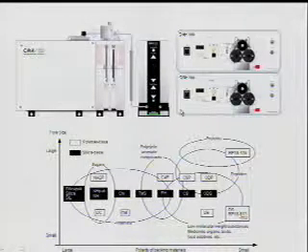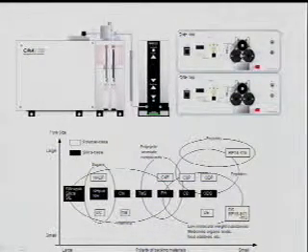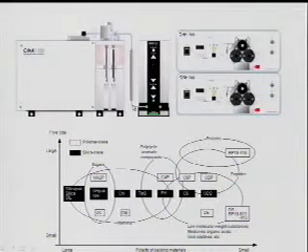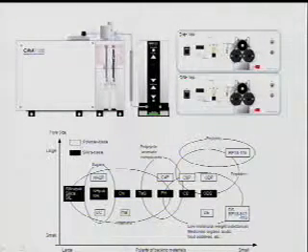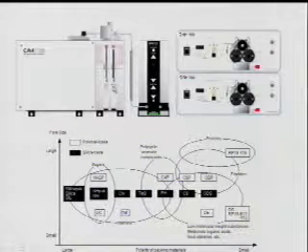This is a high-pressure liquid chromatography instrument, HPLC. The P is also used for performance, high performance, liquid chromatography, so it's liquid. So we have two injectors with the pumps attached to this system. So two samples can be run simultaneously. They are fed through this pre-pump to feed the samples through this filtration column that will clean out any dirt. Then it will pass through the columns. Here we see the two columns. So we can inject two at once, and then these pumps will pump each of those through this system and through the separate columns. So it's a rather sophisticated system. Cost you several tens of thousands of dollars.